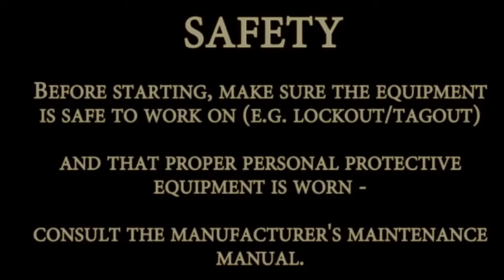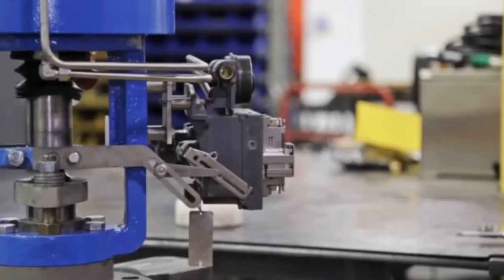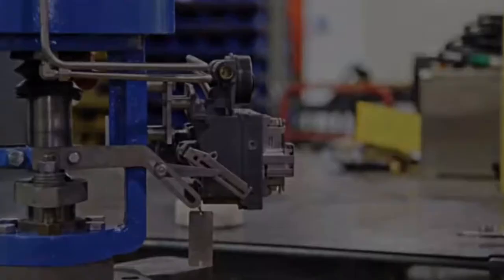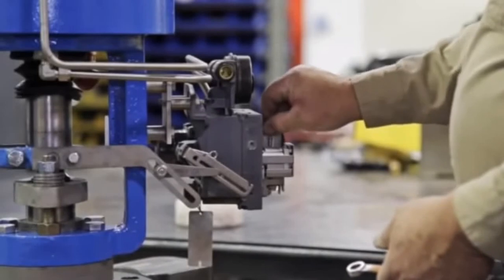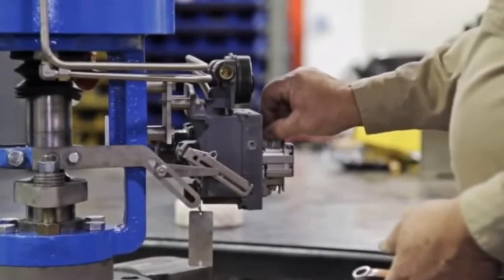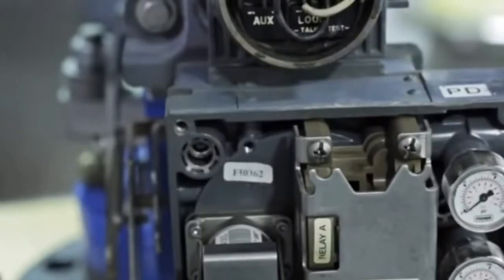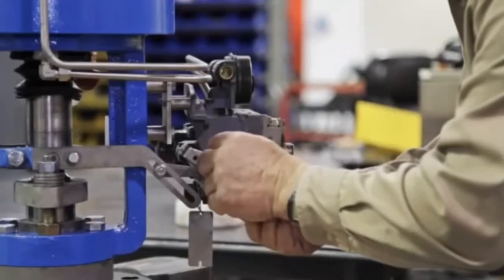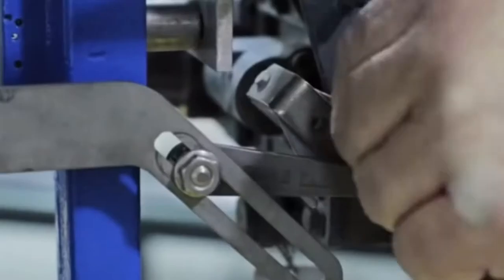We'll start by setting the DVC linkage. First, ensure that the valve is in the default de-energized position, either fully open or fully closed depending on your valve's configuration. Unscrew the alignment pin so we can align the feedback arm to the positioner. Use the pin to align the hole in the feedback arm with the threaded hole in the positioner.